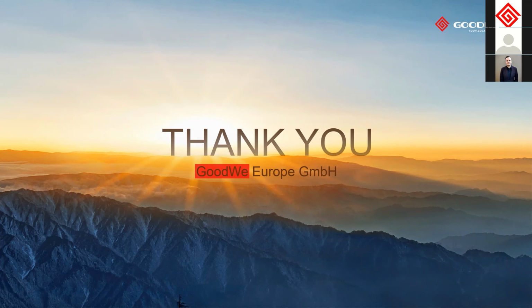So let's start with the first question. The first questions are in the Q&A. Where does the power limit value come from? The power limit is how much you're allowed to export. We have a value there that's also based on your system size. If you're allowed to fully export to the grid, like I explained, you set your full export power limit there. So the full plant capacity you set as your power limit. But if you are not allowed to export any power to the grid, you set that to 0. That's based on the requirements for your site and what the utility company allows you. So that's for export power limitation.